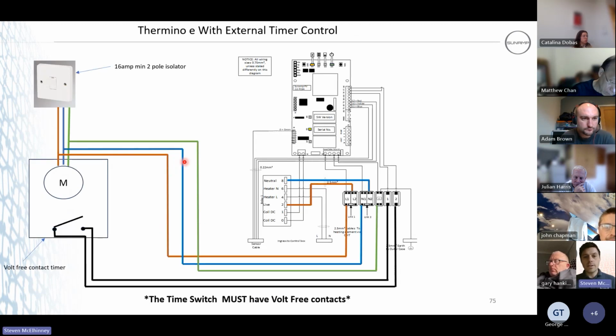With a timer, similar rules apply, but again, we're detecting a demand here. We've got LED D5 illuminated. Nothing's happening. We've got power here, permanent live at the relay, because our volt-free contact timer hasn't made its circuit. As soon as we do that, then everything starts happening. Power starts flowing where it's meant to go. If that timer was to break, we still have that demand there, but it will stop sending power. It will de-energize the relay, which will break the circuit.